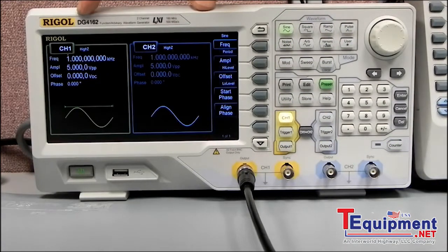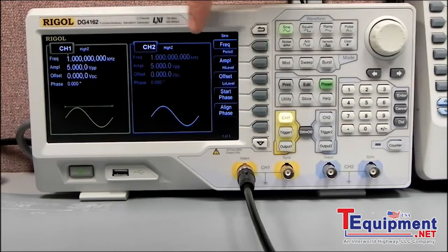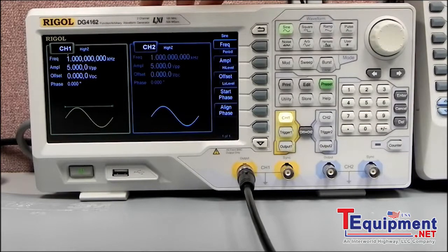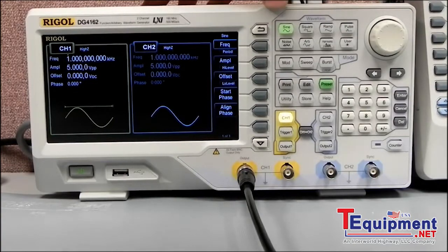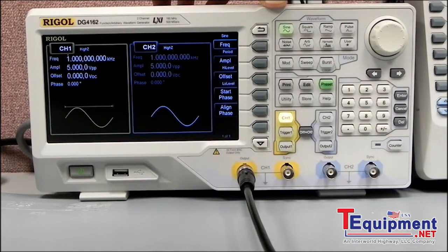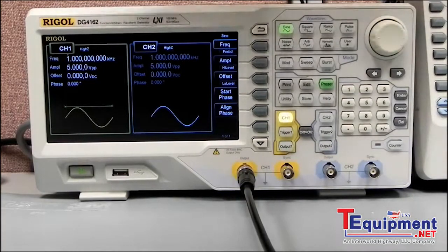You'll see all of the DG4000 models have dual channels. Channel 1 and Channel 2 are identical as far as their power output, voltage and current, as well as all of their capabilities. They each have 16,000 point ARB capabilities, as well as all of the features basically match channel to channel.